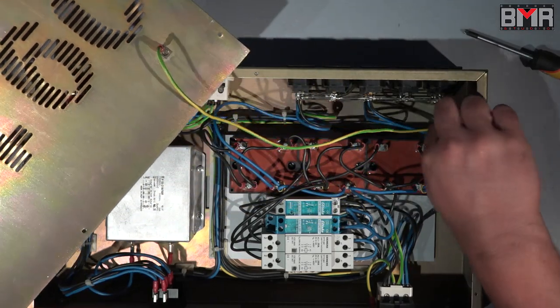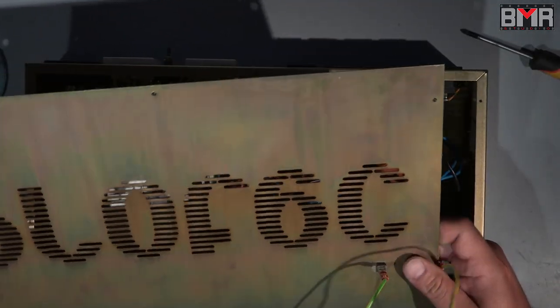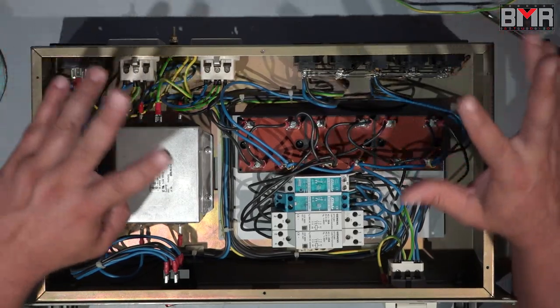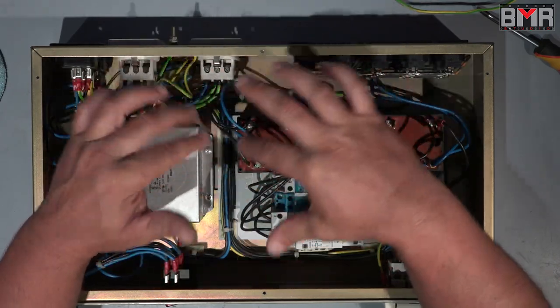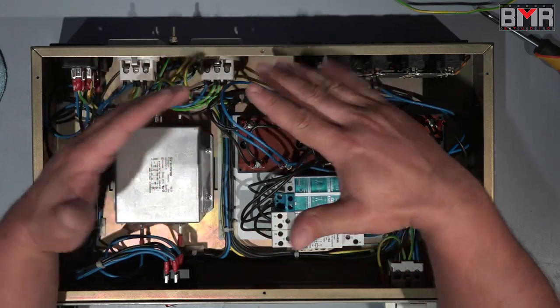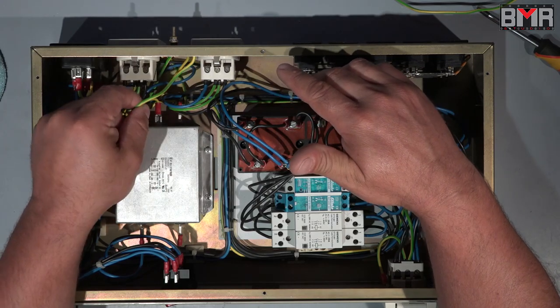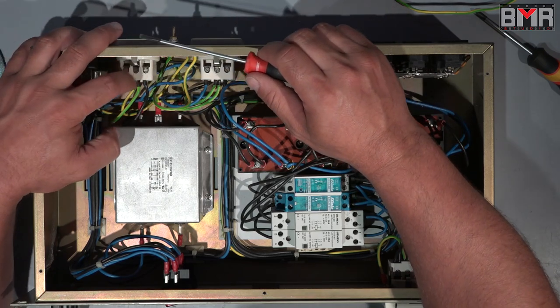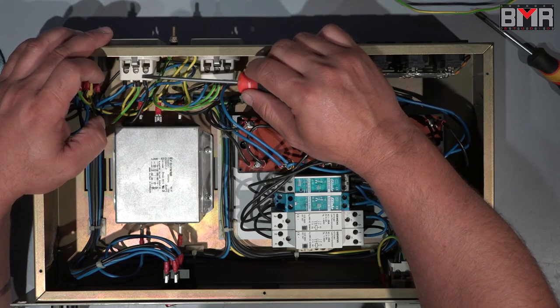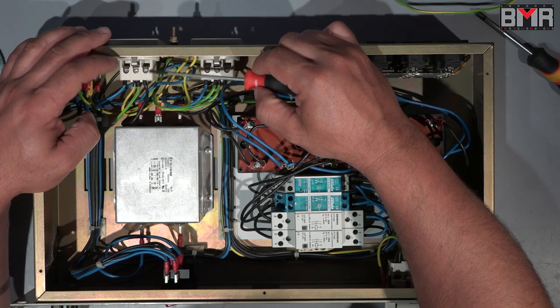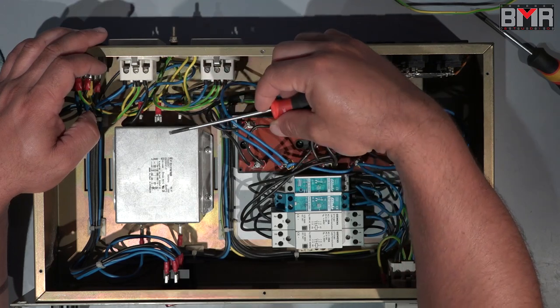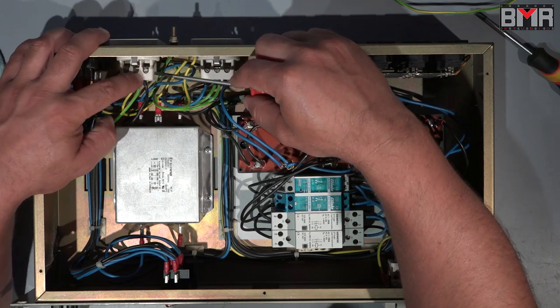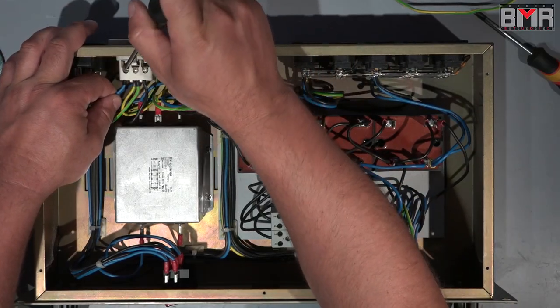Even if the top plate is really thick, really heavy metal, and everywhere is metal, there is a really nice connection between the two plates. But they didn't play with garbage and didn't want to take a risk. So they did here again a proper grounding cable as an extra. Nowadays, nobody is paying big attention to this kind of detail. Even it looks weird, not so elegant and not so electronic, this here is pure black magic of mains voltage and earth.